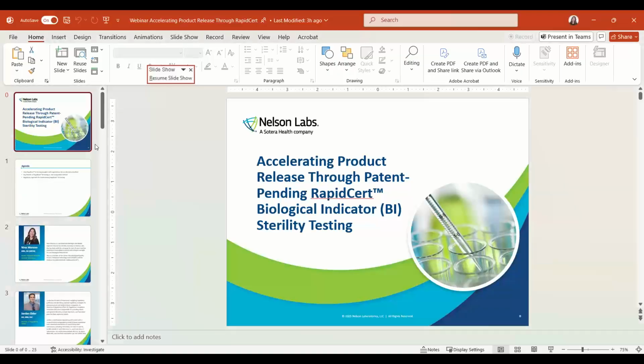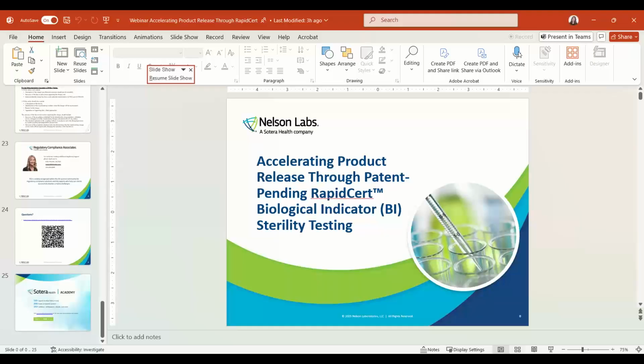Yeah, so the way that this is done is basically the ATP that would be present from any organisms that are within the test container would be enhanced through the addition of specific reagents to the test container. And then from there, there's a luminometer in the equipment that would detect that elevated level of light. And that's how we would measure the presence of the organism, through the relative light units that are evaluated by that luminometer.